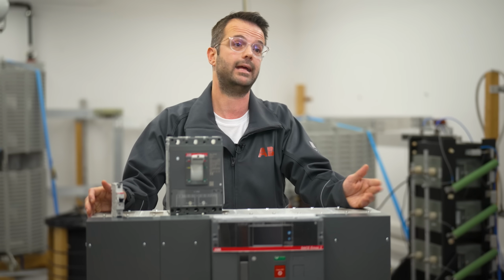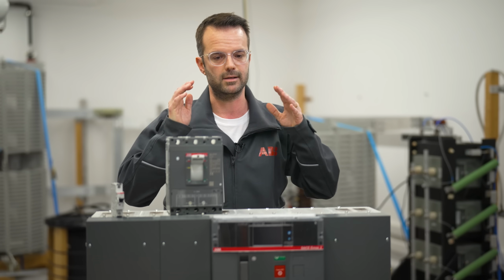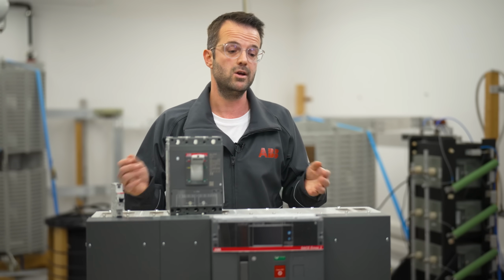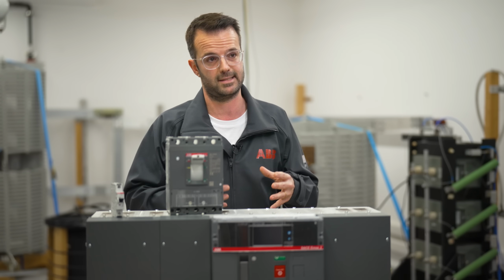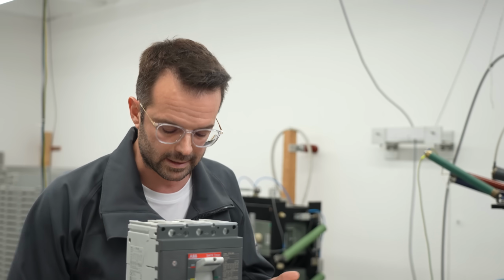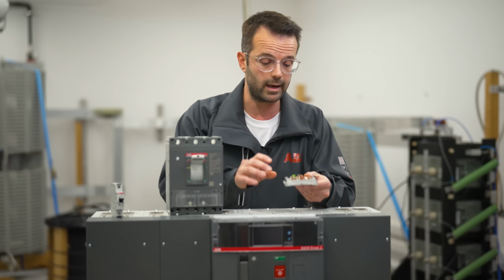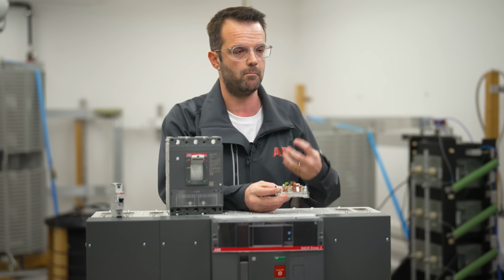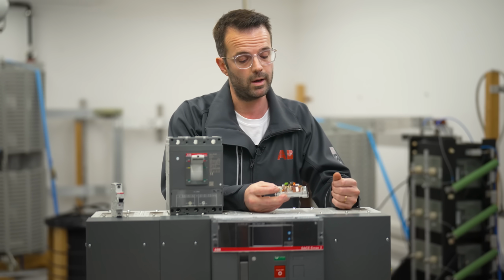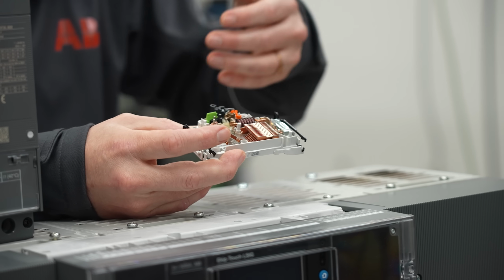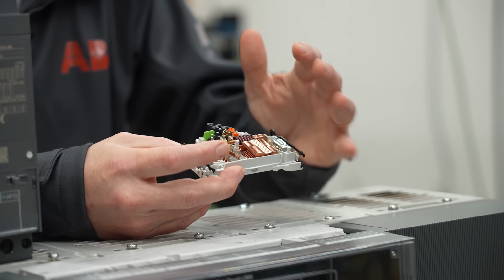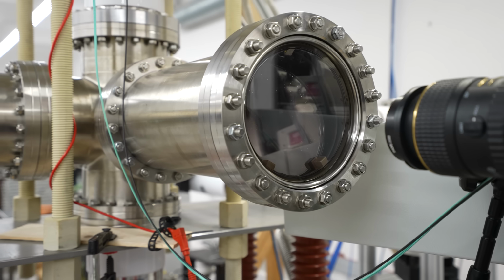In terms of temperature, during a short circuit interruption we have something like 12,000 Kelvin. Just to give you an idea, the sun's surface is 6,000 Kelvin. So during a short circuit interruption, there is a temperature developing which is twice as hot as the sun, which also means that all the materials inside the breaker must withstand this burst of energy without melting or igniting. This isn't just plastic and metal - they're carefully designed to sustain this amount of power.